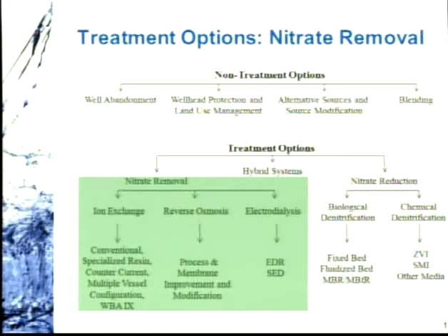So on the nitrate removal side, there's really three primary treatment technology classes. You've got ion exchange and all the variations below that, and I'll talk a little bit about those. Reverse osmosis or high pressure membrane systems, which are driving water through a membrane and by doing so retaining contaminants and salts and other things on the upside of the membrane. And then electrodialysis, which is not used that much. Certainly in the US, it's used a little bit more abroad, but can be used for nitrate removal, and there are some advances in that technology as well.